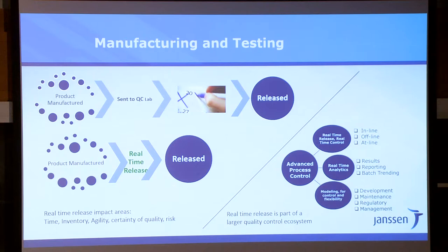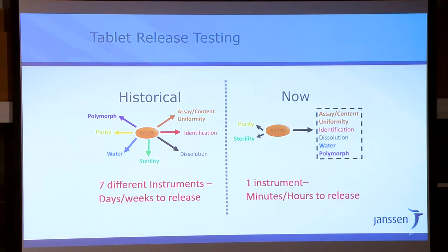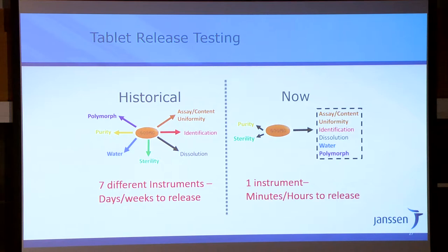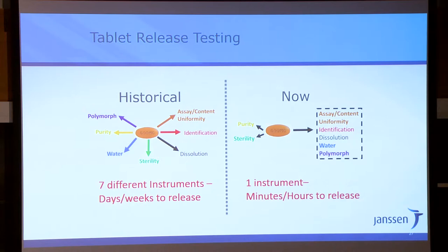Historically, when releasing tablets, we had basically seven tests and many days or weeks to get through all of it — things get backed up in the lab. Nowadays, everything except purity and sterility is done on one instrument, usually in minutes, rather than all taken to a lab for the answer. It has other advantages too: traditionally these things are done by HPLC. HPLC equipment takes a huge footprint, and environmentally the amount of acetonitrile solvent used by these labs is spectacular — it's all sent out for disposal.